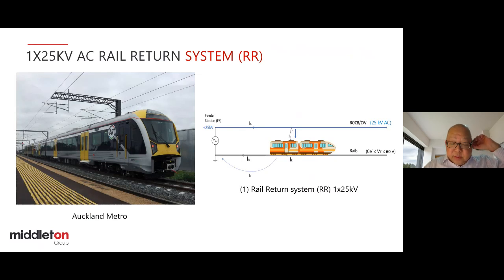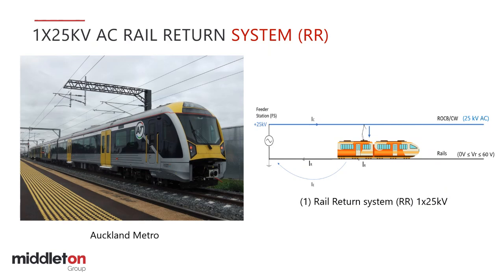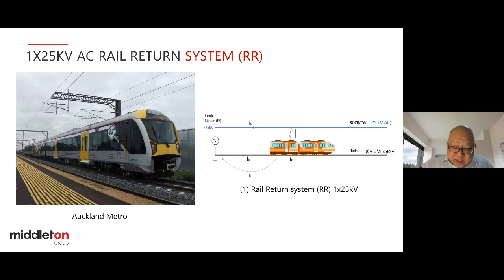This is a very simple rail return system, or RR system. It uses the overhead line, consisting of contact wire and catenary wire, to carry current from the station to the train, and it uses the running rail to return current to the station. This involves leakage current, not stray current. I reserve stray current for DC systems.